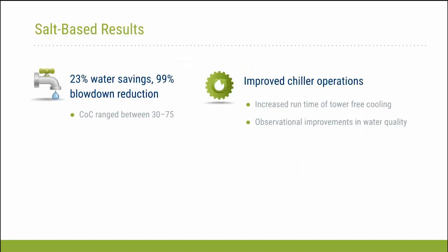So the results that we saw here, I would say, are similar to DWT's. There was a 23% reduction in the cooling tower makeup water and a 99% reduction in blowdown. Of the 3 products that I'm going to cover today, this one had the highest cycles of concentration, ranging anywhere from 30 to 75. But again, as Greg pointed out, once you get above 30, it doesn't really have any benefit. You've essentially eliminated almost 100% of the blowdown. In terms of improved chiller operations, they did note an increase in runtime for the plate and frame heat exchanger and the water side free cooling, and observational improvements in water quality.